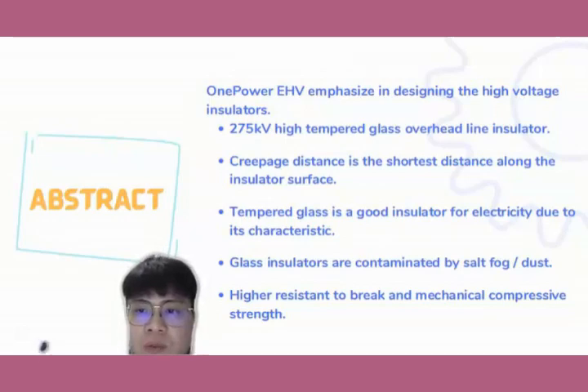Generally, the high voltage insulator is an electrical insulator that impedes the free flow of electrons. So the creepage distance for the insulator is the shortest distance along the insulator surface between the metal parts at each end of the insulator. Creepage distance can also be referred to as leakage distance for insulator. If the surface of the insulator is clean, smooth, and well glazed, the dust particles tend to fall down.